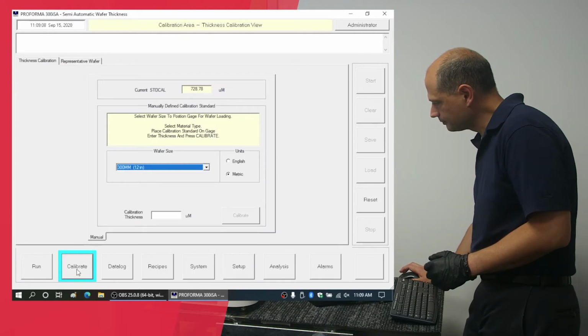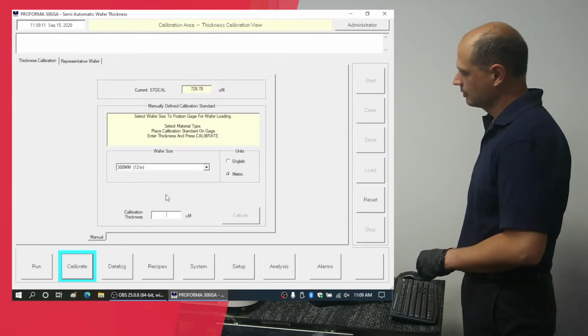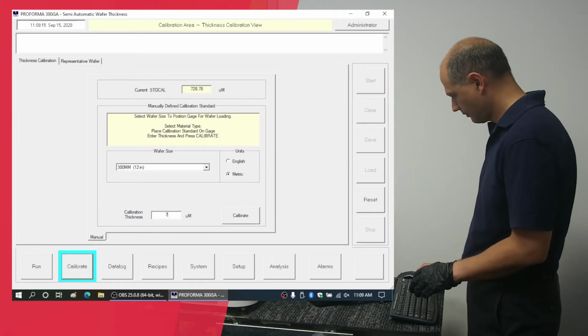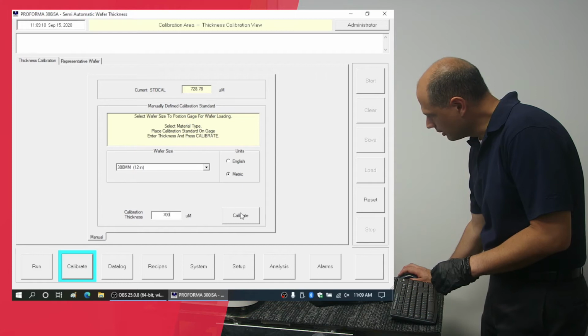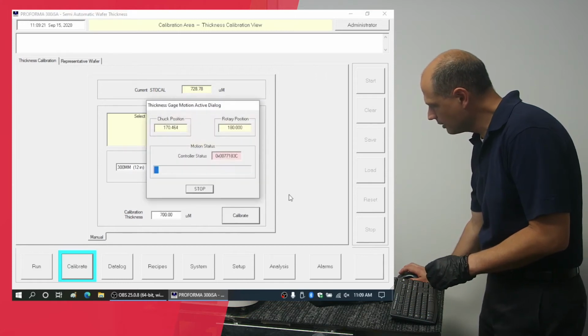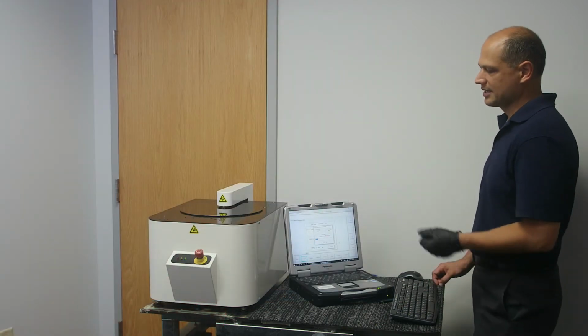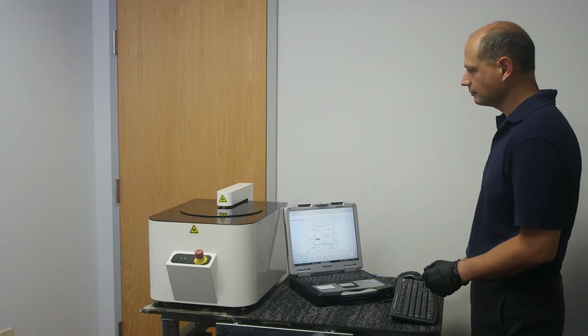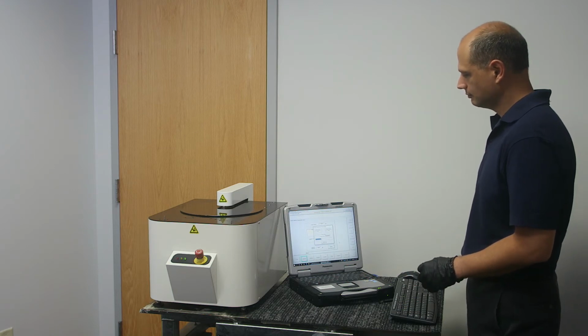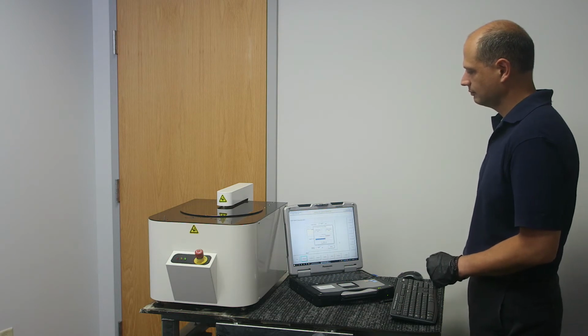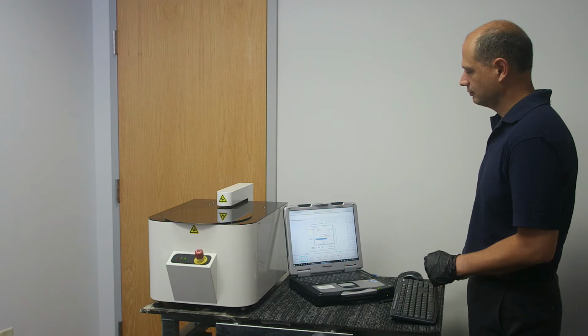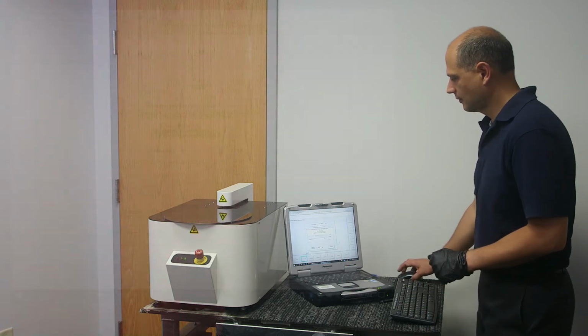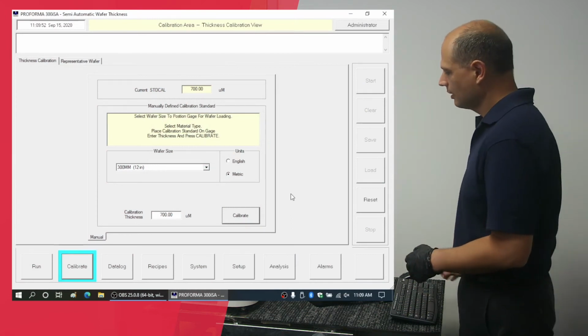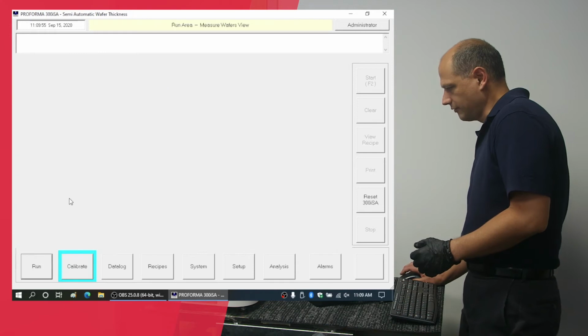Go to the calibrate button and enter the value for the known thickness of that wafer. Click on calibrate. The machine will now calibrate itself based on the thickness of that wafer. Now the machine is calibrated. Now we can start a run of different wafers to measure.